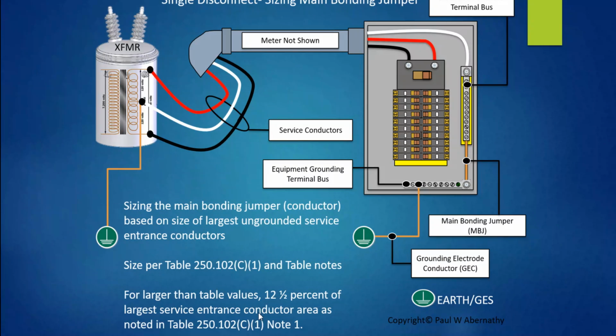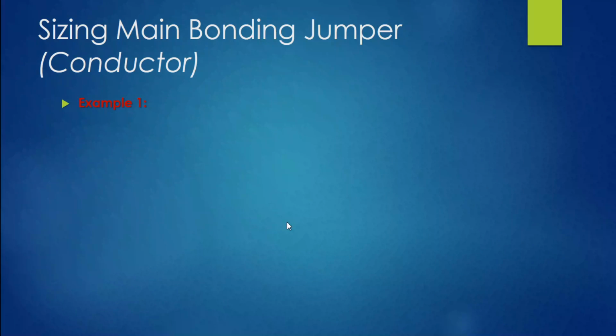Now, a key note: if the values of these conductors are over 1100 kcmil copper or 1750 aluminum, then you have what's called Note 1 to that table, and we'll see that in a minute. That's where 12.5% of the largest service entrance conductor, or the area if they're in parallel, kicks in. Don't worry, we're going to cover all that to make it really easy to understand. All right, let's do an example. We're going to work through this together.